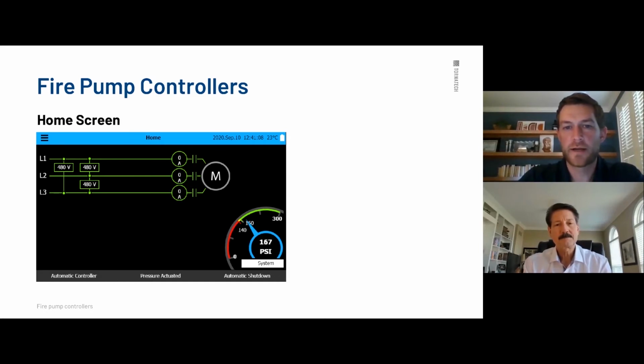Also down here on the bottom right, you'll see it says 167 PSI. That's your system pressure. You can actually tap on that, which I can't do, but on the real panels you can tap on that and it'll pop up even bigger on the screen. So if you're doing a pump test or something and you need to see what kind of pressure, you can tap on that. It makes it a lot bigger and you can see it from across the room. You can see that it's got 140 as the cut in. So we have on this gauge here, which says 0 to 300.